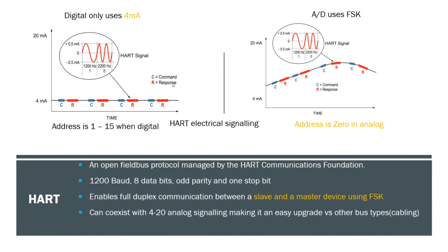The master commands information, saying, hey, I want to know something, and the slave responds back with that information, represented here in the graph. So this could be, tell me what your process variable is right now, and the response will be, my process variable is 100 PSI. Inside this data package, there's the number 100, and a bit that tells you it's PSI or percentages or whatever it happens to be.